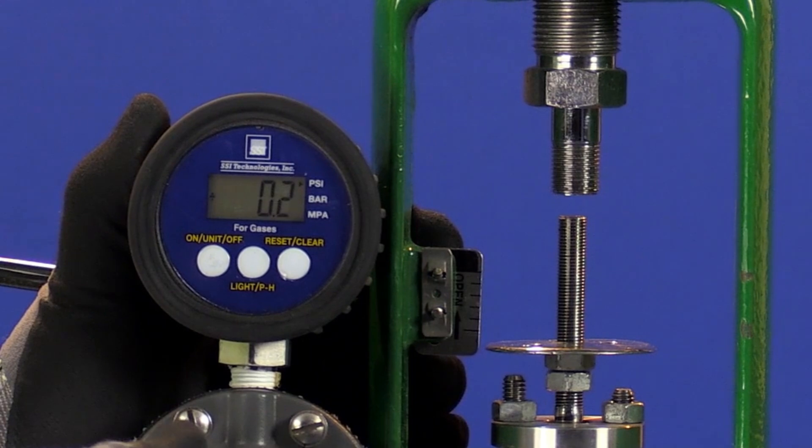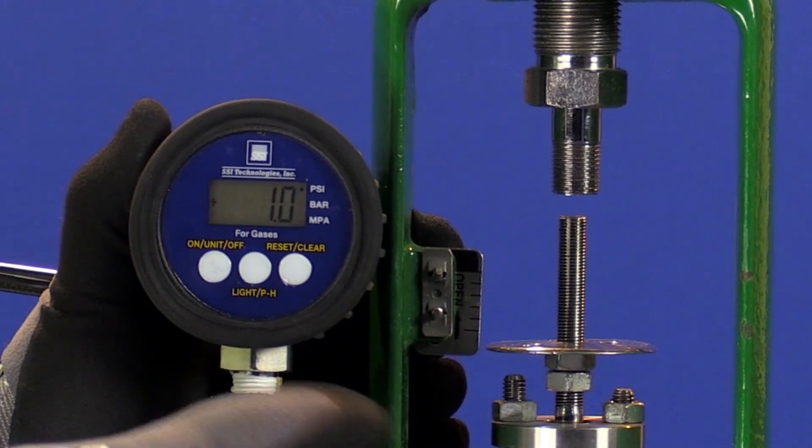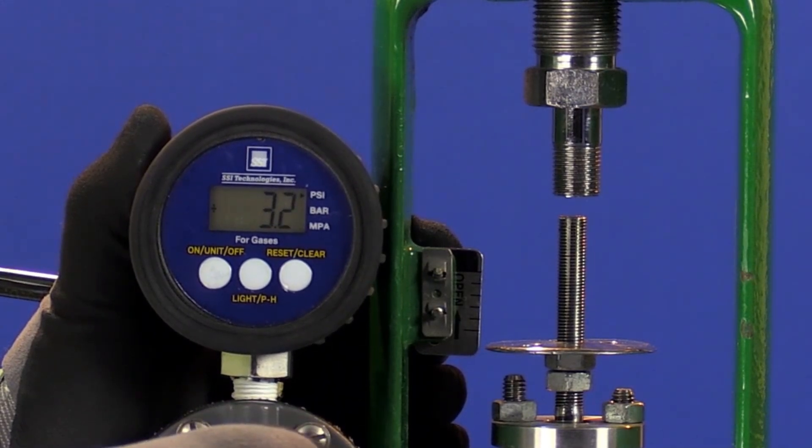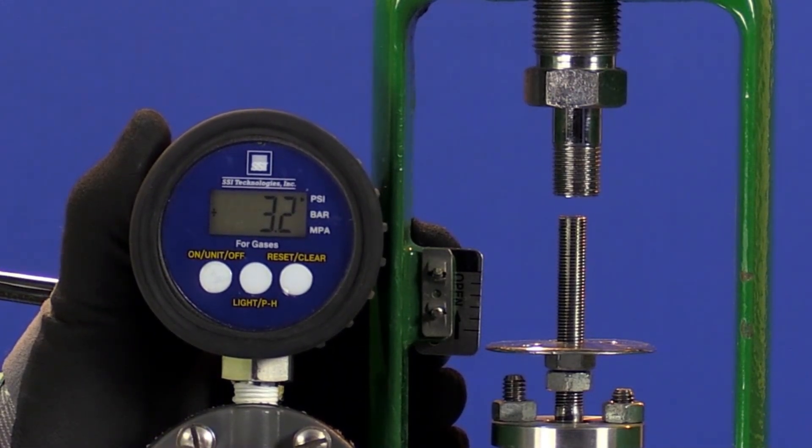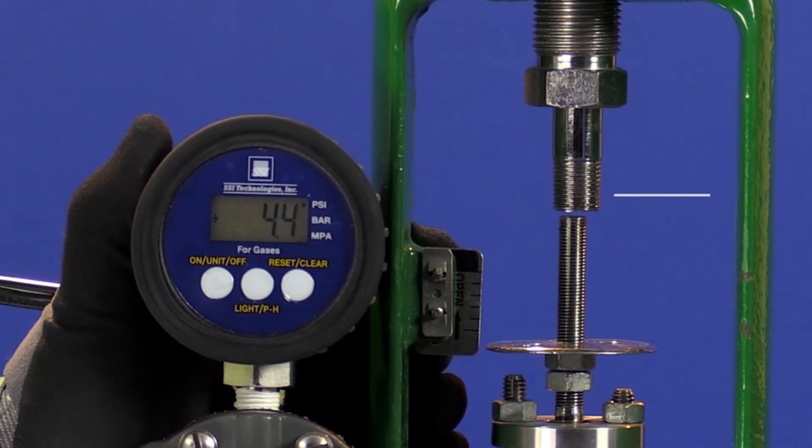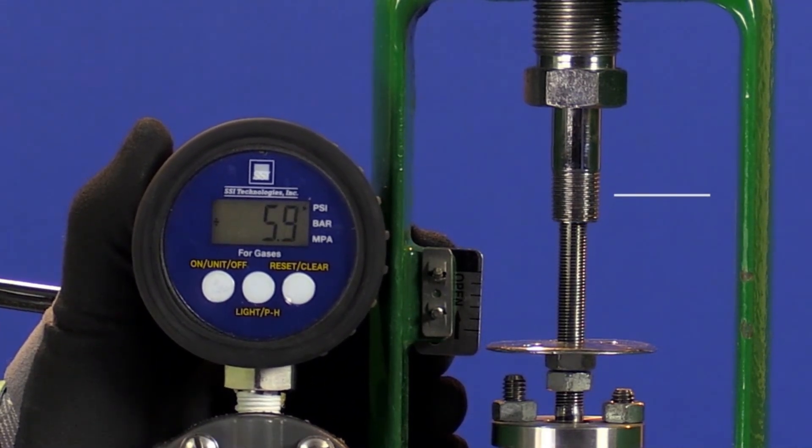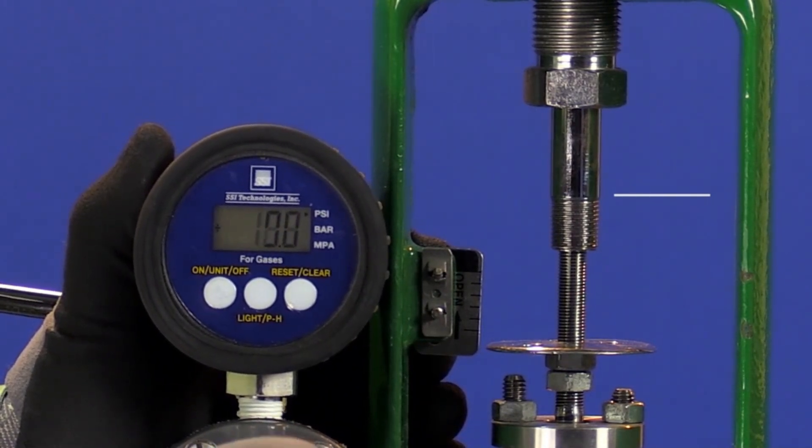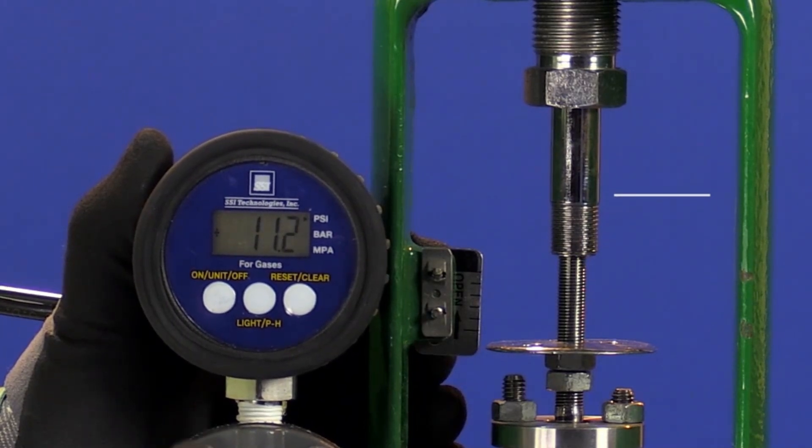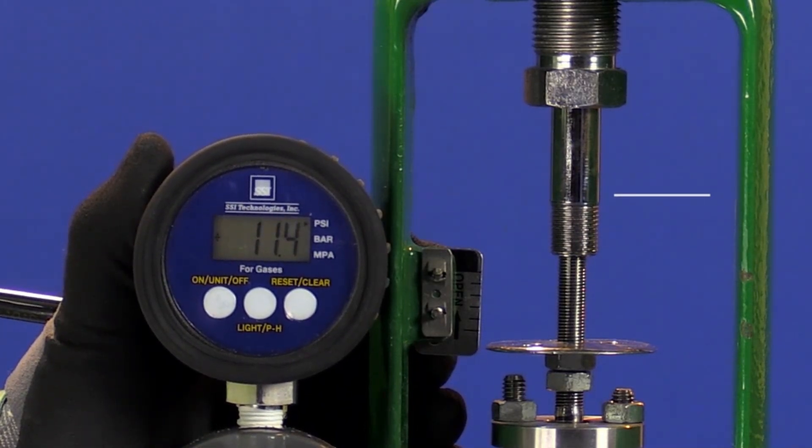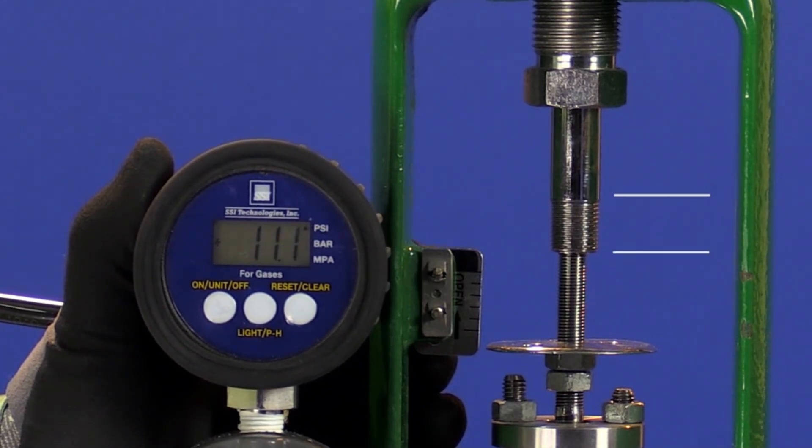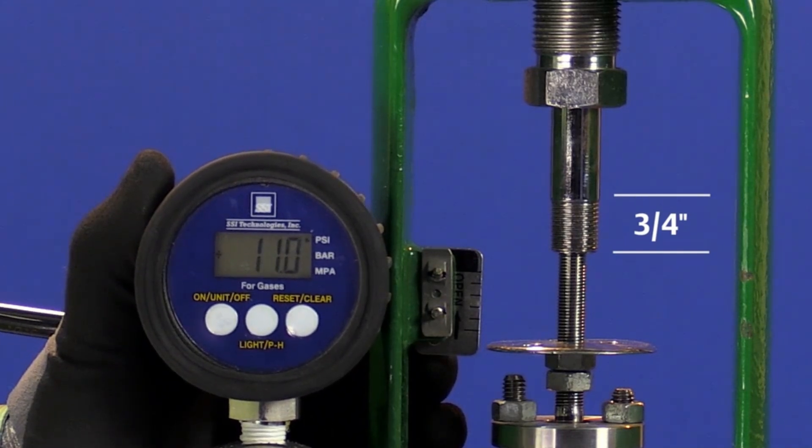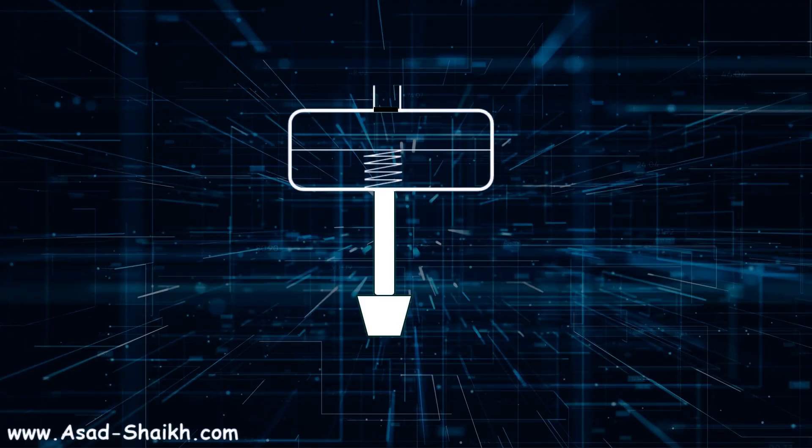At 0 psi, the spring is pushing the actuator to the upper travel stop. Bench set is always calibrated from the upper travel stop. The stem does not move as I increase the pressure from 0 to 3 psi due to the initial compression of the spring. At 3 psi we see the first movement of the actuator. This pressure where the initial movement of the actuator stem is detected is the lower bench set value. As I continue to increase pressure in the actuator, the stem continues to stroke down. As I approach 11 psi, I have reached the rated travel of the valve, three quarters of an inch.